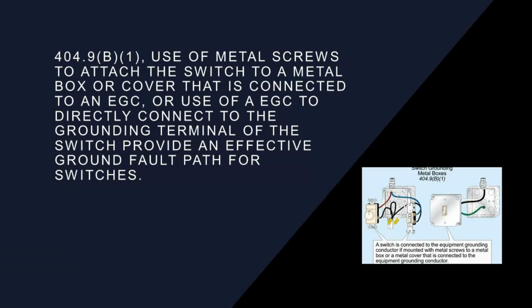.9(B)(1), the use of metal screws to attach the switch to a metal box or cover that is connected to an EGC, or the use of an EGC to directly connect to the grounding terminal. Kind of already touched on this one too. We talked about it for receptacles, but now we're going to talk about it with switches. So if you look at this little switch in the diagram over here, this is what I call an industrial cover. It is actually not rated to carry a ground. Those 10-24s that go on each corner of that box, the threads are too large. There are not two threads touching, so those industrial covers need a pigtail back to the box.